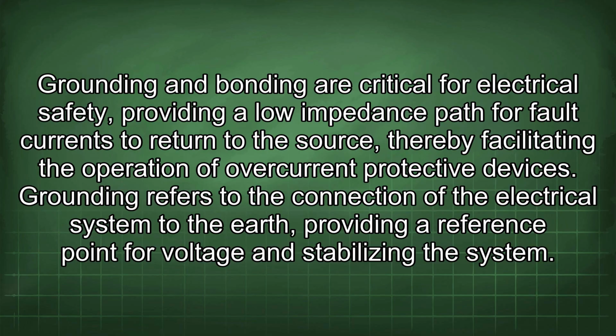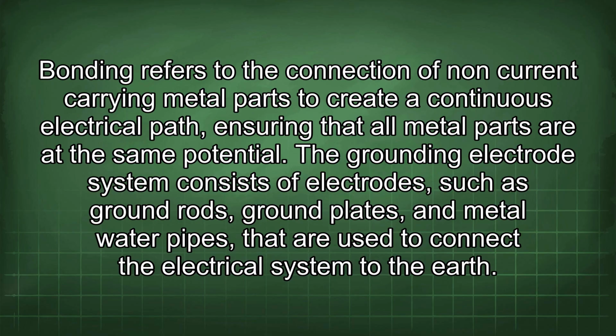Grounding and bonding are critical for electrical safety, providing a low impedance path for fault currents to return to the source, thereby facilitating the operation of overcurrent protective devices. Grounding refers to the connection of the electrical system to the earth, providing a reference point for voltage and stabilizing the system. Bonding refers to the connection of non-current carrying metal parts to create a continuous electrical path, ensuring that all metal parts are at the same potential.